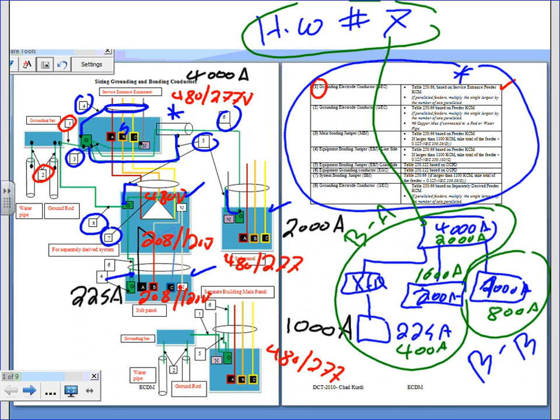2000 amp feeding 1600 amp direct and an 800 amp direct. And through a transformer, we're feeding a 400 amp. What are you required to do? You're required to size all the bonding and grounding conductors for this system. Here's how the system is put together. Now, would it make a big difference, guys, if I added another 15 panels like this, sub-panel? Same way, same sizing, same way of calculation.